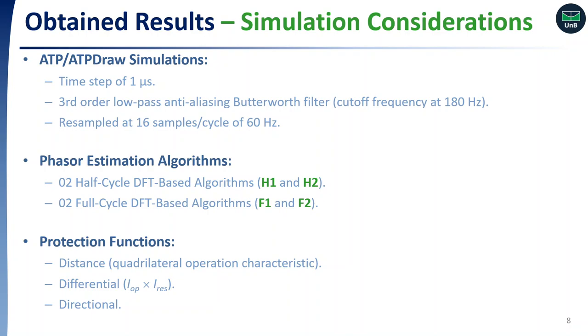In order to do that, ATP/EMTP simulations were carried out using a time step of 1 µs. Then, a third-order low-pass anti-aliasing Butterworth filter with cutoff frequency at 180 Hz was applied, and the signals were resampled considering a sampling rate of 16 samples per cycle. Two half-cycle and two full-cycle DFT-based algorithms were implemented. We assessed transmission line protection performance in the near vicinity of the LCC-HVDC link, considering the distance protection function with quadrilateral operating characteristics, differential protection function, and directional protection function.